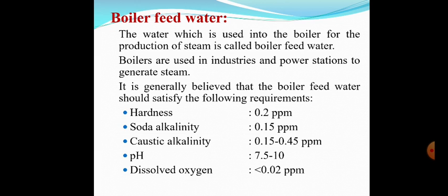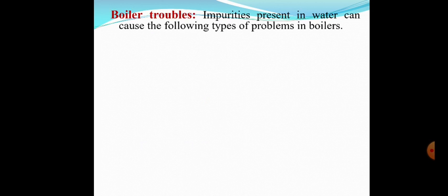Therefore, it is generally believed that boiler feed water should satisfy the following requirements: hardness should be around 0.2 ppm, soda alkalinity should be in the range of 0.15 ppm, caustic alkalinity is in the range of 0.15 to 0.45 ppm, pH is 7.5 to 10 which is a basic pH, and dissolved oxygen should be less than 0.02 ppm.